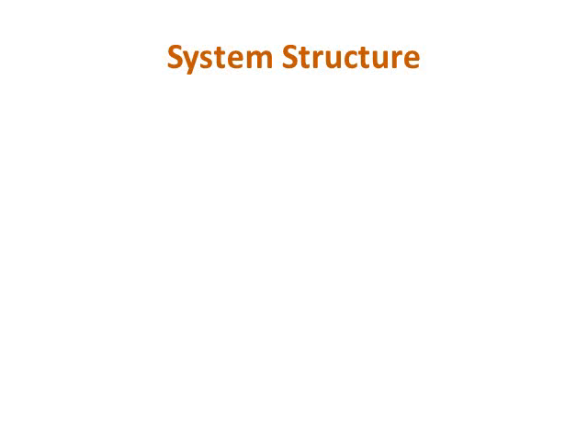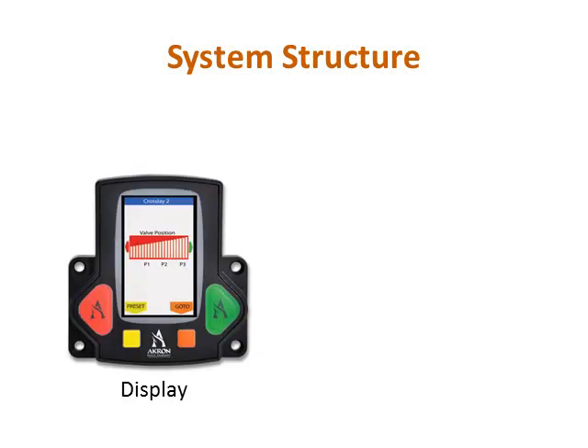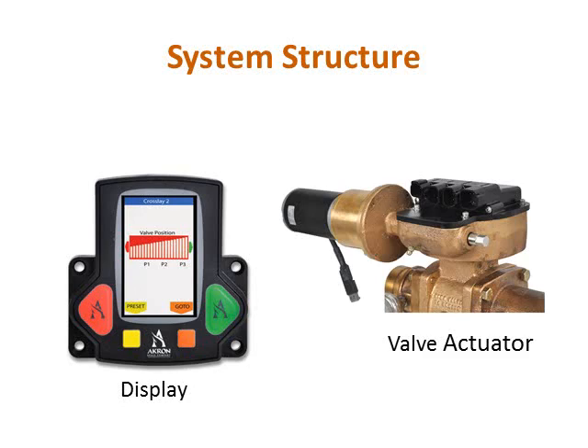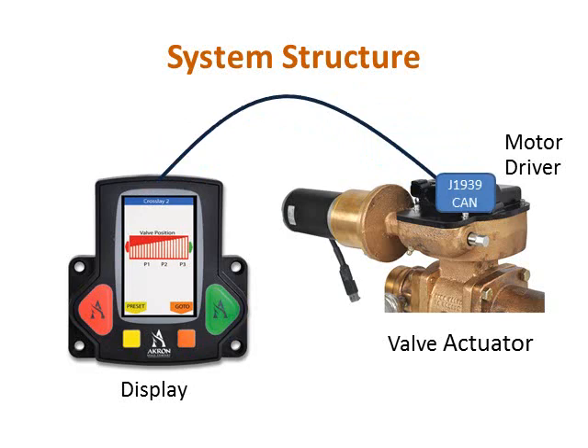The new Navigator Pro system is structured a bit differently than previous systems. It contains two pieces. The first piece is the display, and the second piece is the motor driver. The display functions as a user interface only. It displays information about the valve position and sends signals to the motor driver that tell it to open or close the valve. The motor driver is mounted on the valve actuator. It's the brains of the system and has many important functions. The circuitry inside the motor driver is responsible for driving the motor open and closed, as well as reading pressure and flow. The two pieces are connected via a J1939 CAN connection and communicate over that connection.